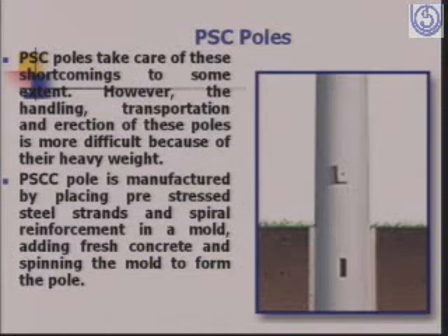Then we have the pre-stressed cement concrete poles. They are known as PSC or PSCC poles. These PSC poles take care of the shortcomings to some limit. However, the handling, transportation and erection of these poles is more difficult because of their heavy weight. The pre-stressed cement concrete pole is manufactured by placing pre-stressed steel strands and spiral reinforcement in a mold and adding fresh concrete and spinning the mold to form the pole.